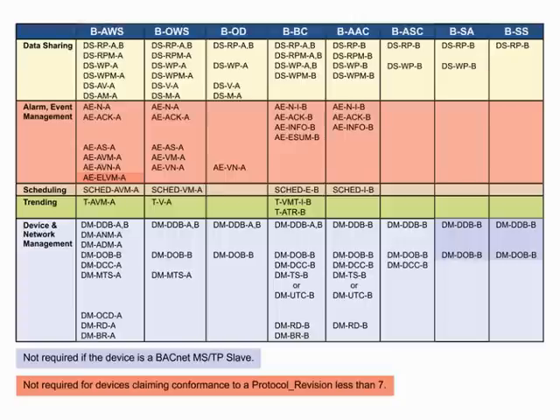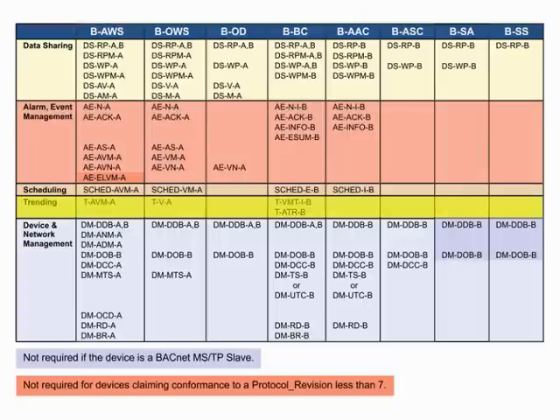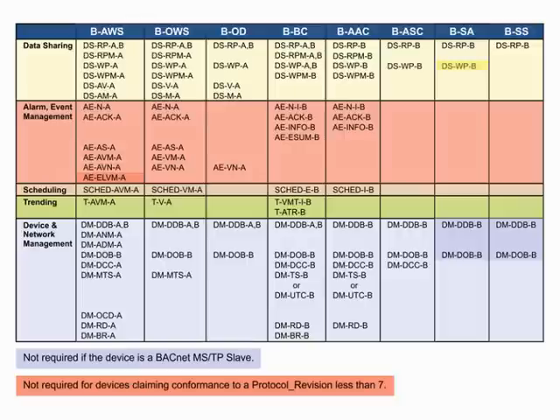The Smart Sensor does not have to support alarming, scheduling, or trending. If it is an MSTP slave device, it does not have to participate in the discovery process. The same is true for the Smart Actuator, B-SA, but it must support write property — otherwise, we could not output a command to the actuator.